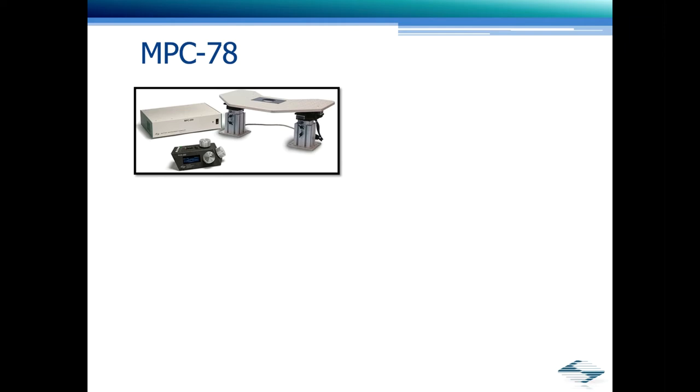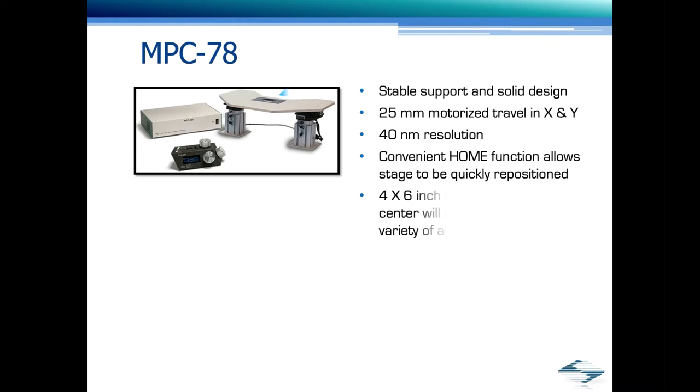Next, we have the MPC-78 stage. Features include stable support and solid design. 25 millimeter motorized travel in both X and Y. The MPC-200 controller provides 40 nanometer resolution steps. Convenient home function allows stage to be quickly repositioned. 4x6 milled pocket at the center will accommodate a variety of aluminum stage inserts. We also have custom aluminum inserts available.